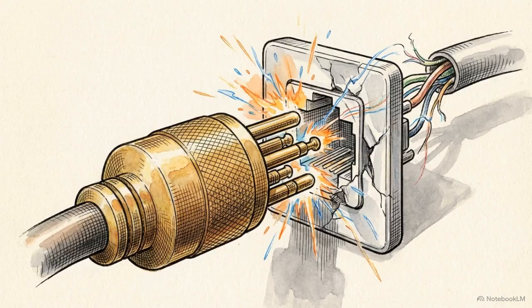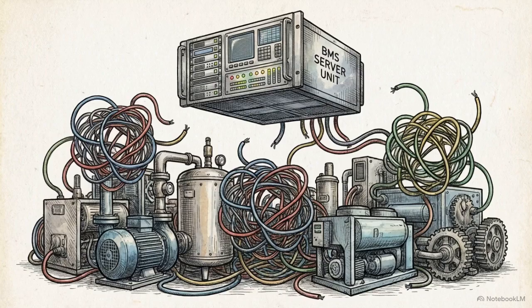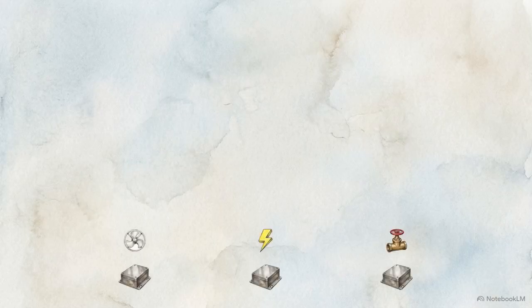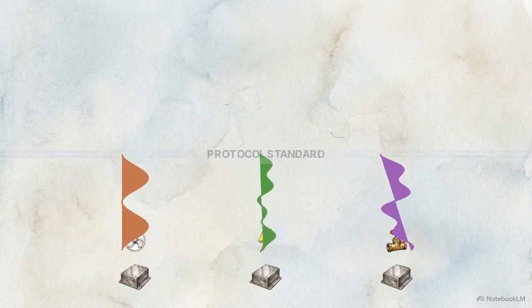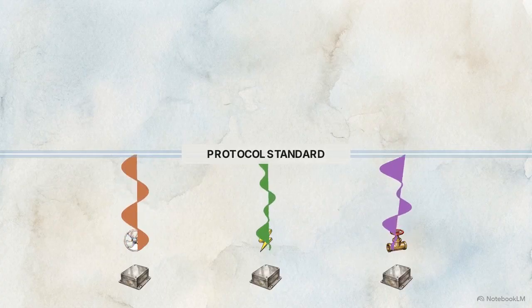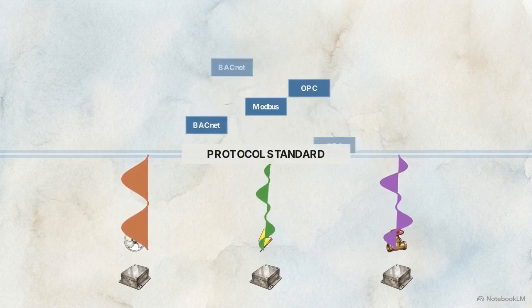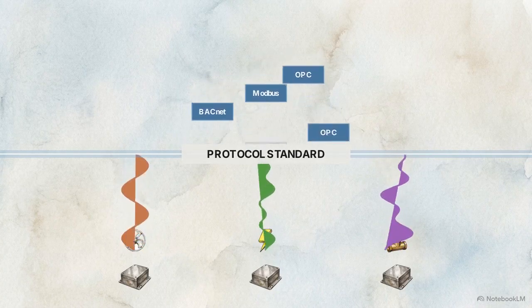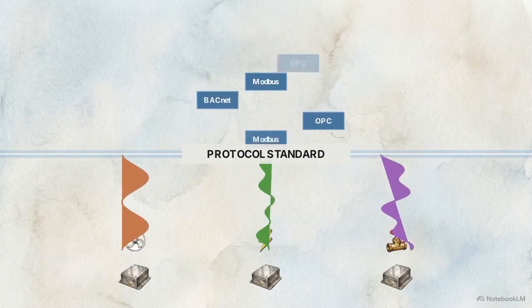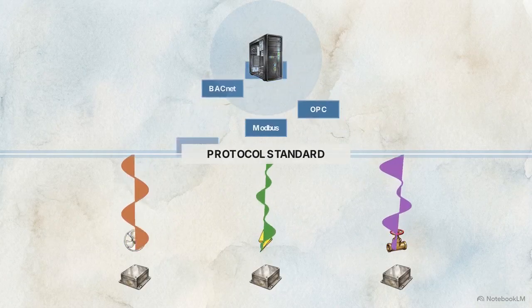But connecting Tier 2 to Tier 3 presents a major technical hurdle: getting the localized DDCs from varying manufacturers to successfully transmit data to the central server. The solution relies on communication protocols. A communication protocol is a standardized set of rules for formatting and processing data. To unify a building, engineers rely on strict industry standards: BACnet for HVAC equipment, Modbus for electrical meters, and OPC for complex industrial processes.